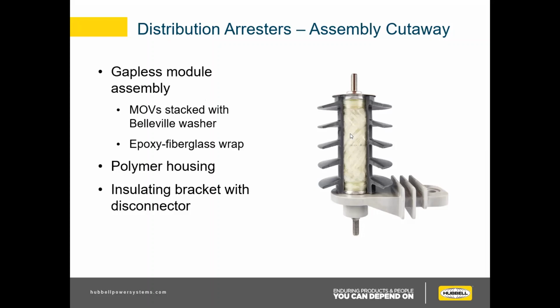Our MOVs are stacked with a Belleville washer in the middle, and they are compressed between two aluminum terminals, and I want to say around 750 foot-pounds or so. It kind of depends. Then they're wrapped with a fiberglass epoxy, put in an oven and cured, so they expand a hair, but they're super durable. Then they are inserted in a polymer housing with two end plates on each end, and then an insulating disconnector bracket that we'll go over a little bit in a minute.